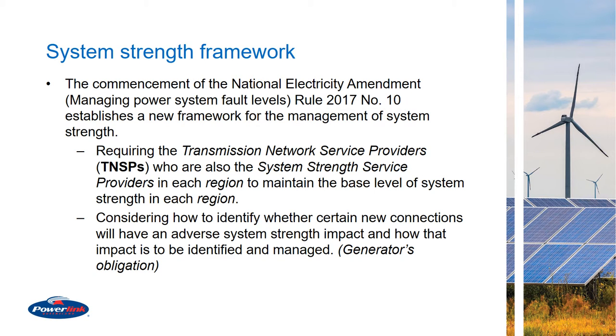The System Strength Framework was first introduced in 2017 by the AEMC. And basically, as part of this framework, different obligations were put on AEMO, NSPs, and generators. The other point to highlight is that in the current System Strength Framework, system strength is referred to and measured as fault level, whereas we as a whole industry have learned that system strength is more than just fault level.